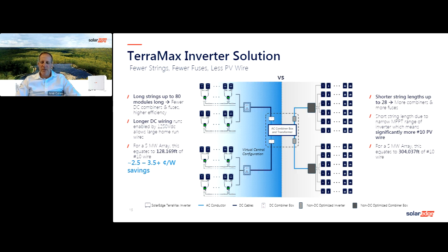So what does that mean? If I'm able to go to much longer strings, I'm able to get some cost out of the design. Putting on my designer, engineering, EPC hat, if I'm able to get hundreds of thousands of feet of 10 gauge PV wire out of the design, if I'm able to cut my number of combiner boxes by half, or even two thirds, because I don't have strings of 25 modules, I have strings of 60 or 70, that means I have a third or a half of the DC combiners in my array, less fusing, less everything. That is capex - straight up cost that I can design out. I'll show you what that looks like in a second.